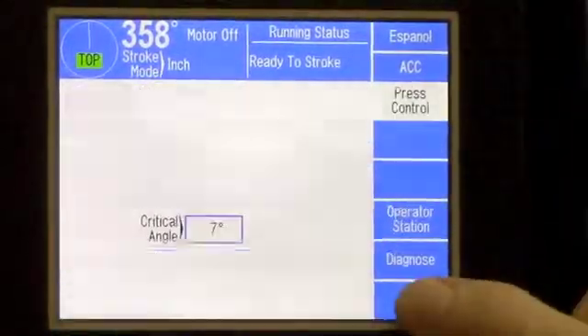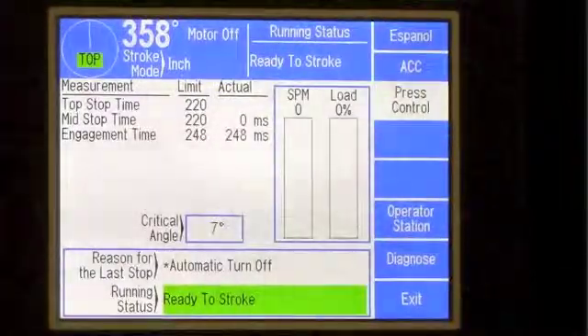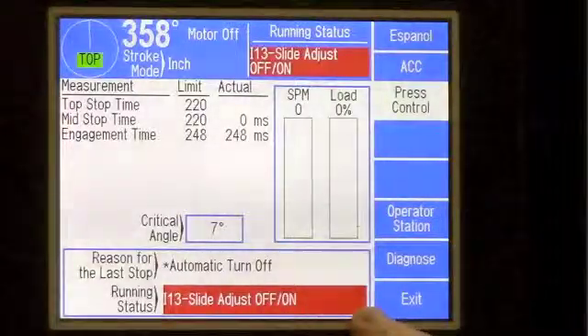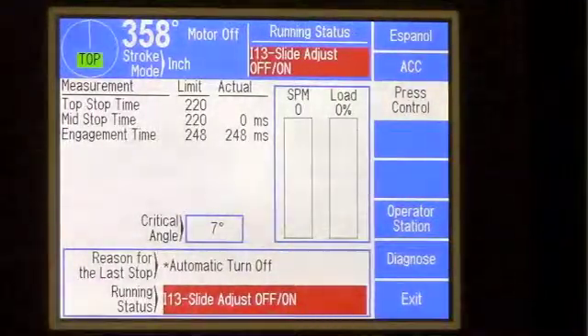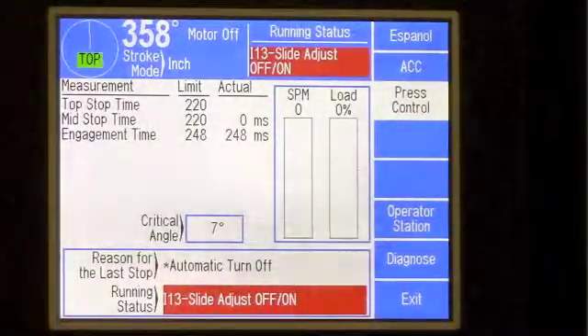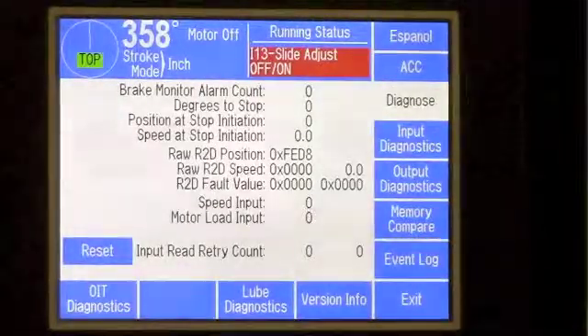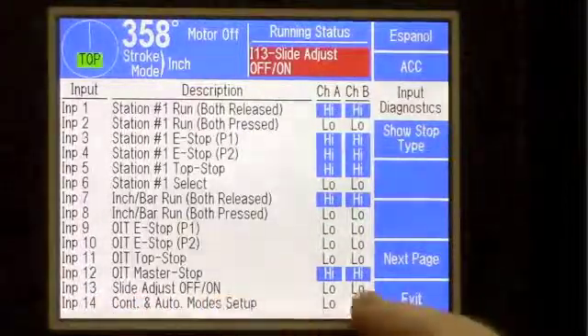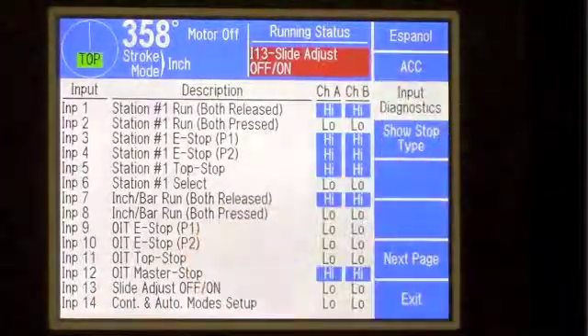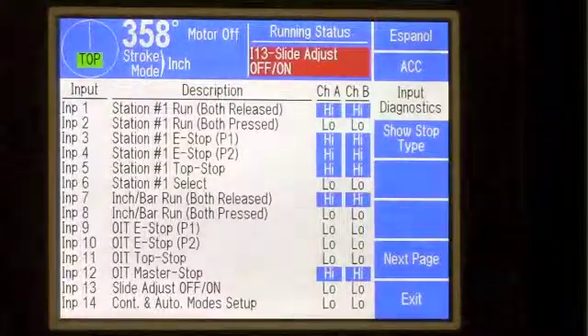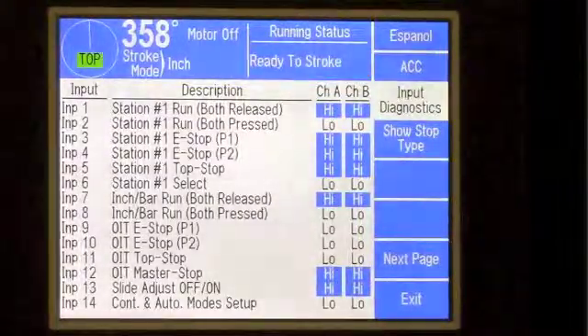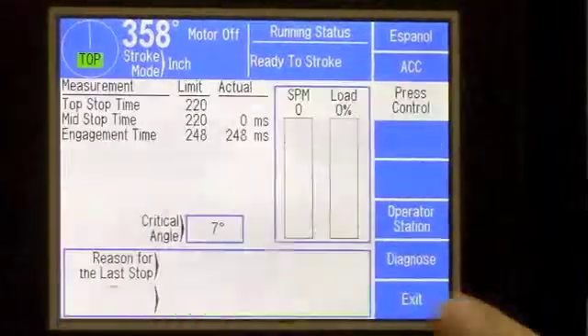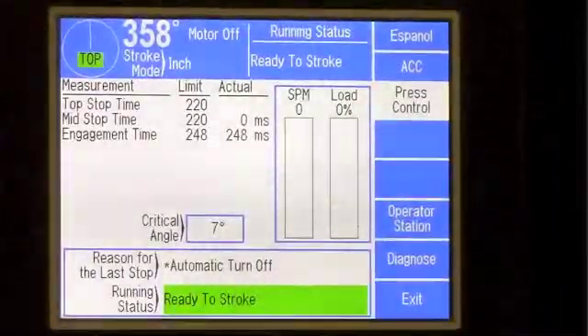If you have a problem on your current running status — for instance, our slide adjust key is made — you can see the display will go red and it will say 'I13, slide adjust.' From that, we go into our diagnostics menu, input diagnostics, and we can see input 13 is low. That is what's giving us our fault. Simply switch that to the off position. As you can see, that input has now changed to high, and our current running status is ready to stroke.